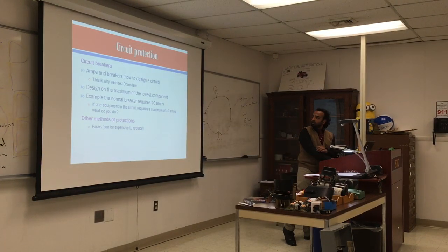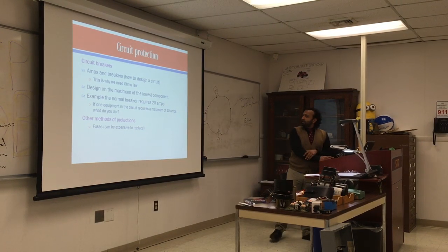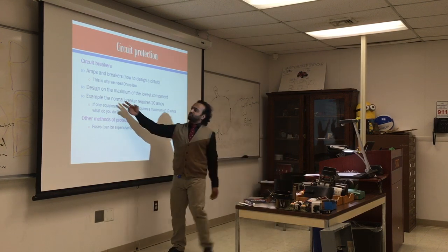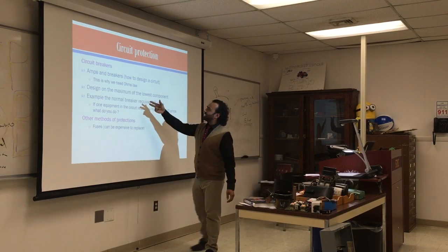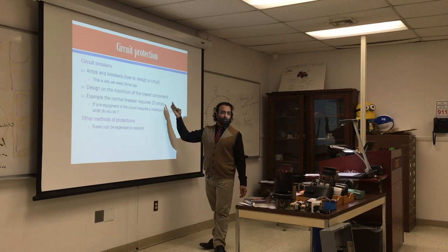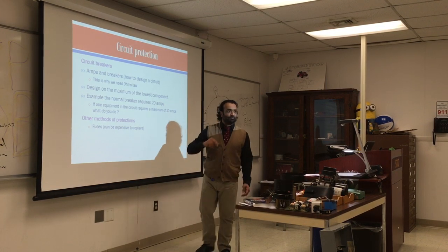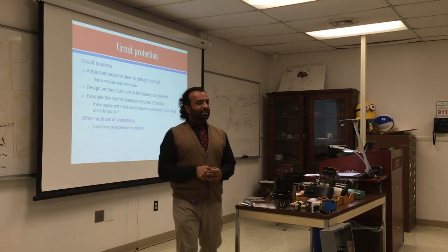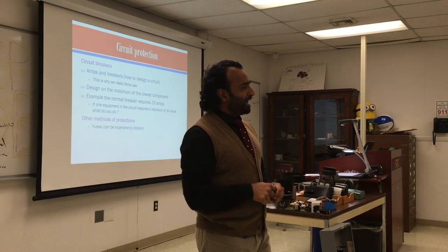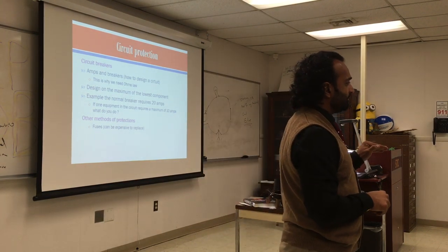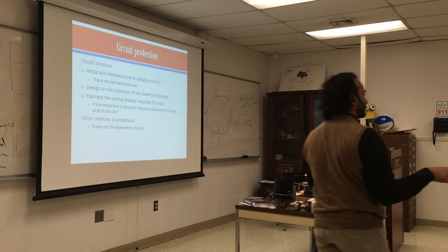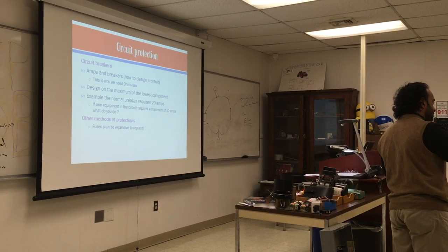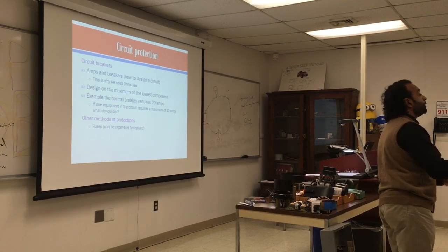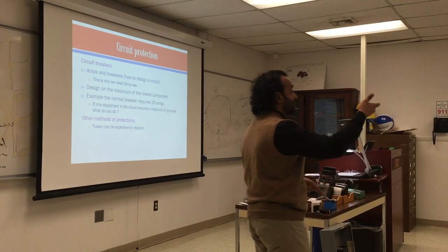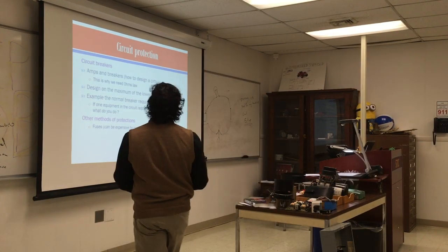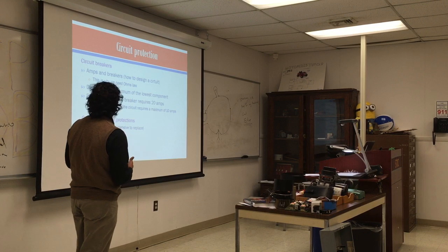Okay, so fuses. When we design a circuit, we will design for the maximum of the lowest component. So if the maximum amperage draw for your microwave is 15 amps, you design for the 15 - the lowest component in the circuit. So in case it surges, it will trip. You're not going to design for the maximum higher component, you're going to design for the lowest. Otherwise, give it its own circuit.